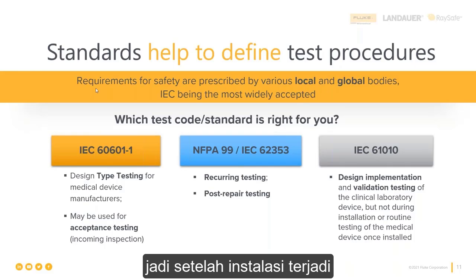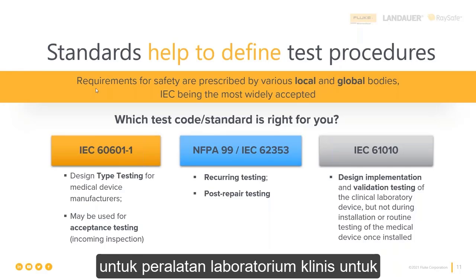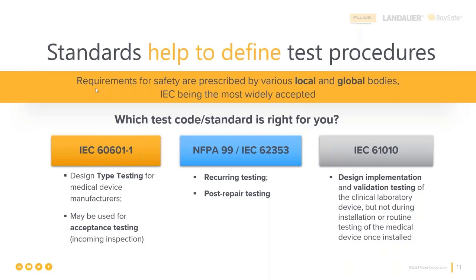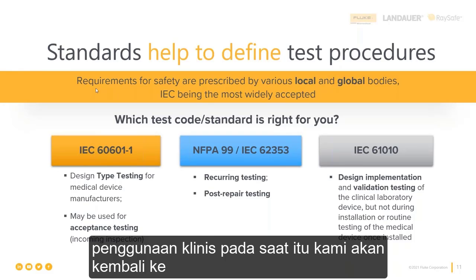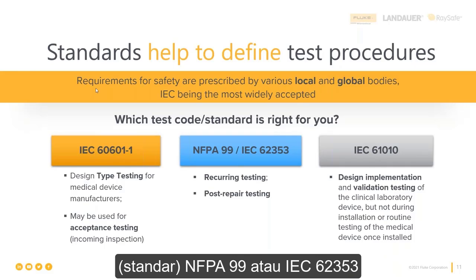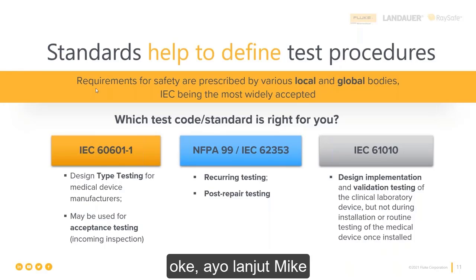So after the installation has occurred and we have the turnover for the clinical lab equipment for clinical use, at that point we would revert to NFPA 99 or the IEC 62353 for further periodic testing. Okay, go ahead, Mike.